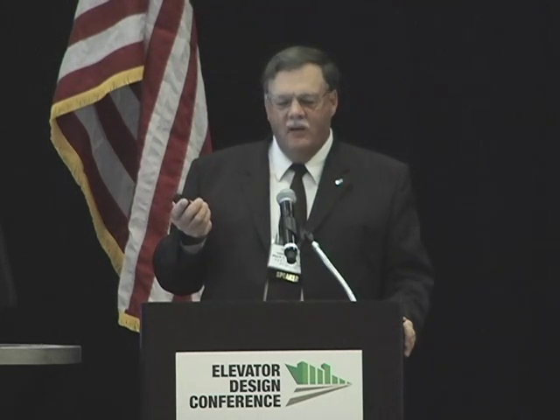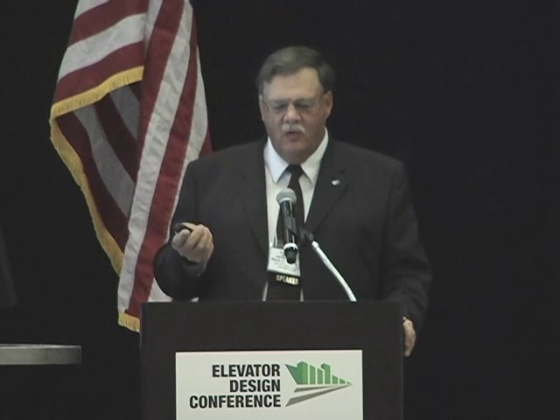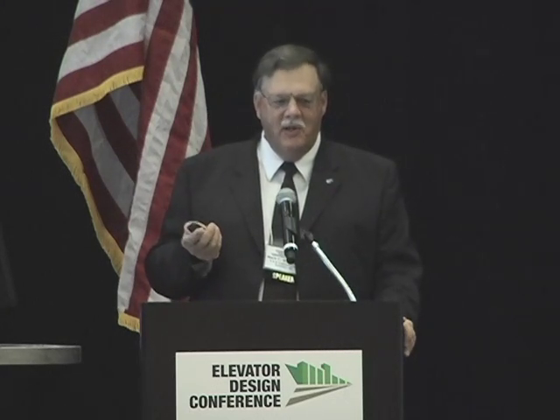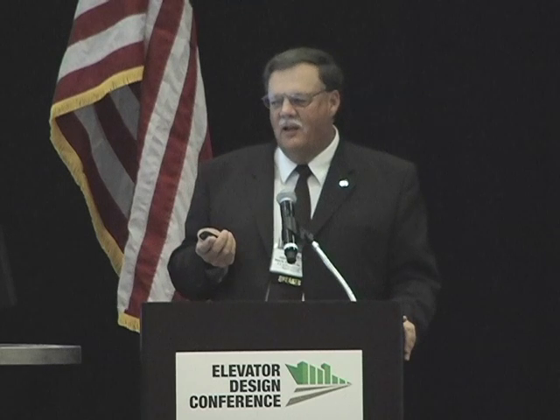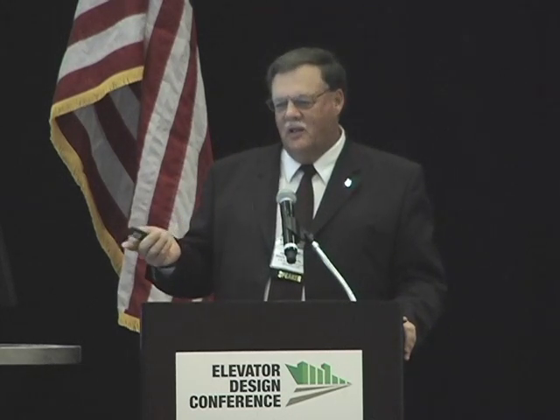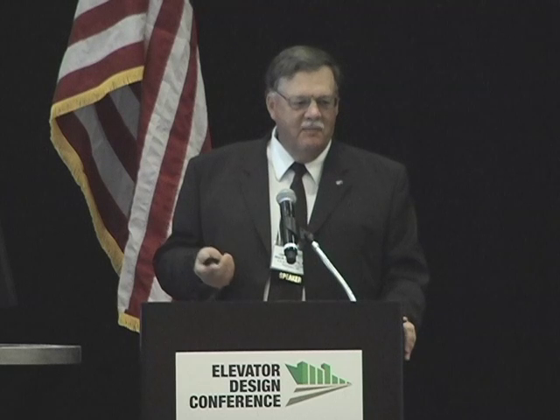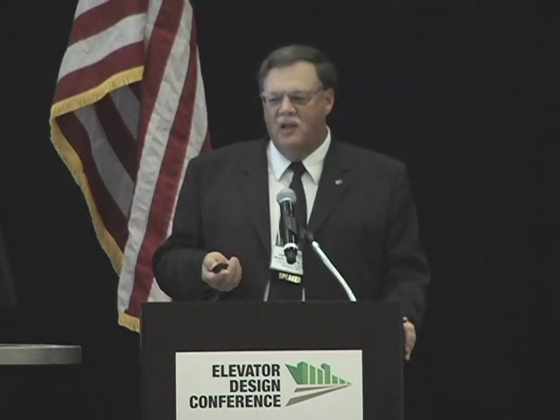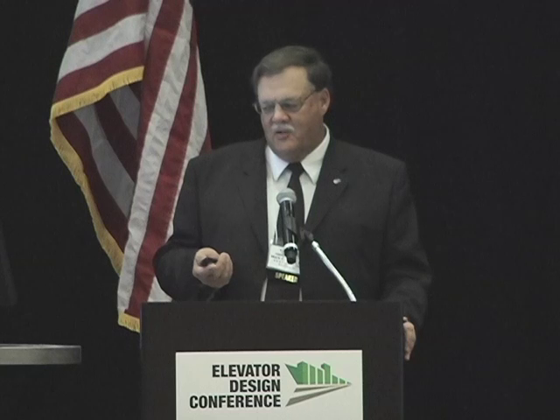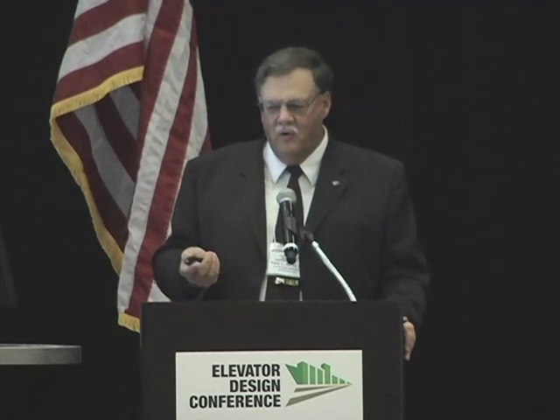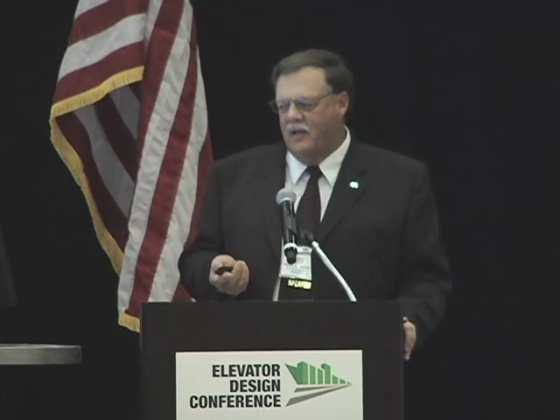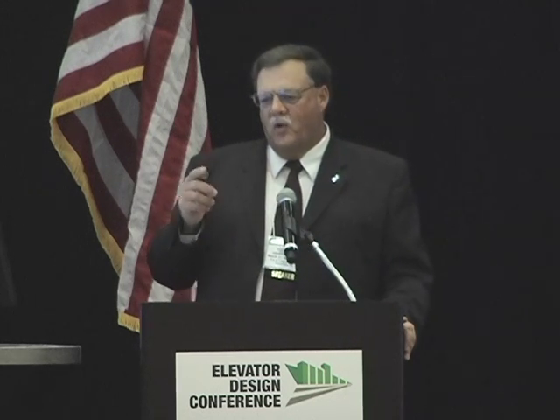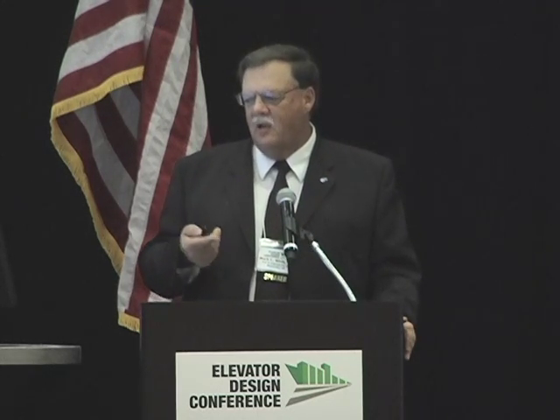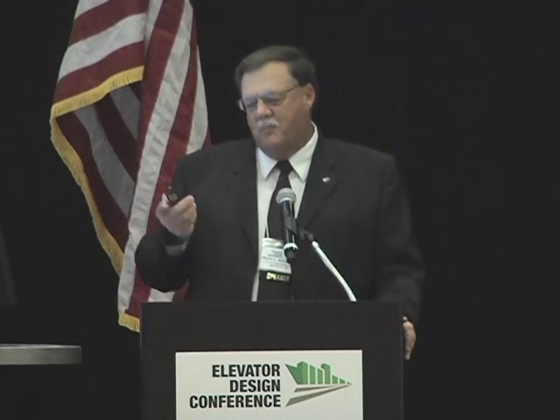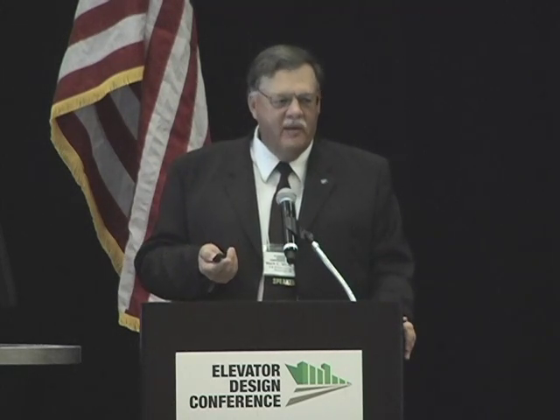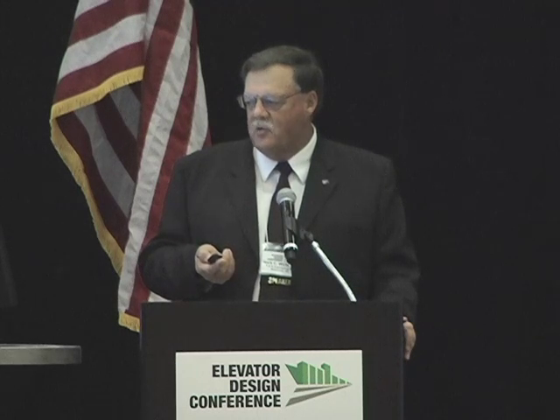I've only been able to get one power company to let me ground their neutral like this in the last 30 years. I did it once in California. Usually, to build a high Z system like this, you have to have your own transformers. Most utility companies and metering groups can't seem to figure out that it really won't hurt them if you do it this way. But it does have a lot of advantages of avoiding the ground fault tripping problems and controlling voltages. And I promote this wherever I can. You're seeing more and more of it these days in industrial power systems.